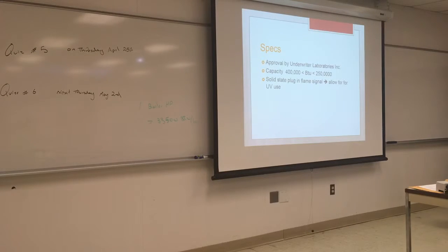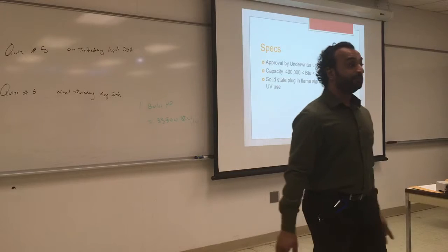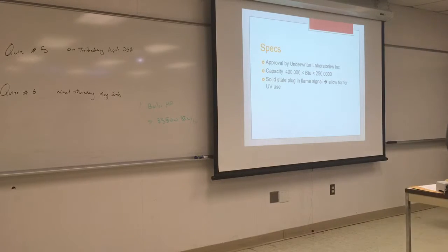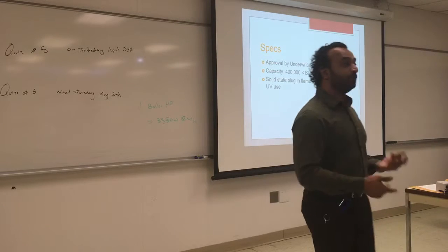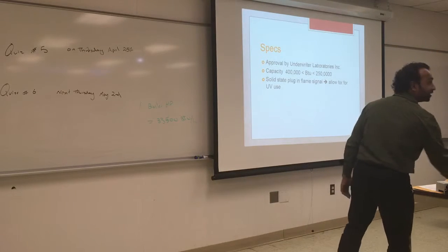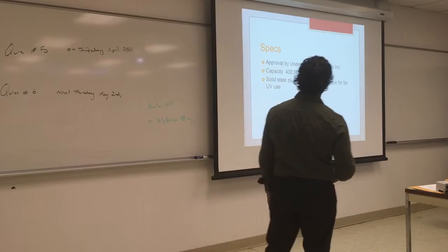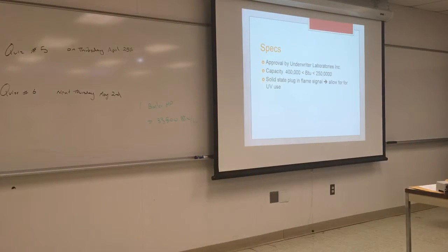Does it just program itself? Yeah. You're gonna have to have a scan. No, no. So it's already pre-programmed. You put it in there, and it will change the entire logic of the pre-purging and post-purging and the operating controls. So you can use different signals. They try to make it more interchangeable. They want to keep this like a single stream where they have the same controller, but you can change the logic.